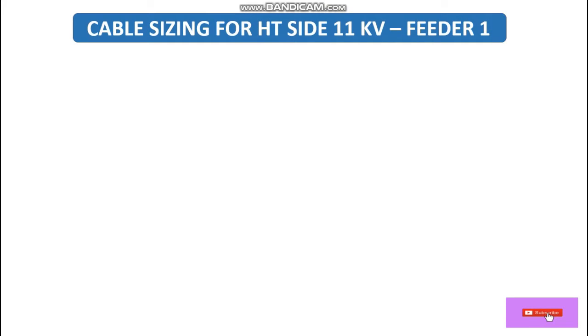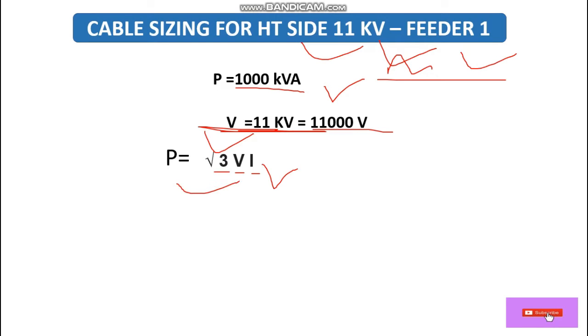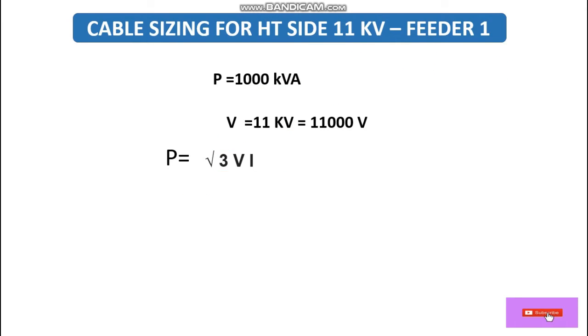Cable sizing for the HT side — that is the 11 kV Feeder 1. The capacity of the transformer is 1000 kVA, which is the apparent power. The HT side voltage is 11 kV from the point of supply, which is 11,000 volts. The formula for apparent power is: S = √3 × V × I, where I is the full load current. Using this formula, we calculate the full load current.